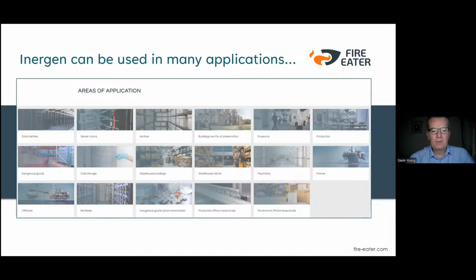An interesting one is in the likes of CT scanners in hospitals. We had an incident recently in Denmark where there was a fire and the sprinkler system activated, and it suppressed the fire, but it didn't extinguish the fire.